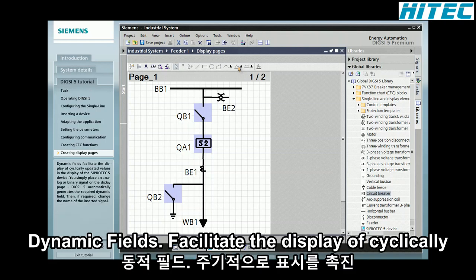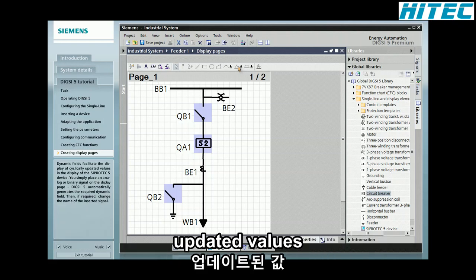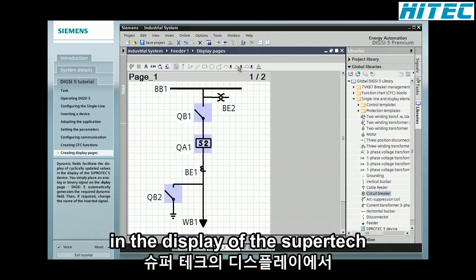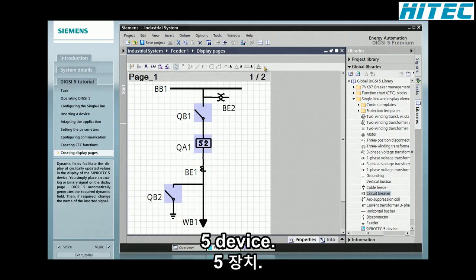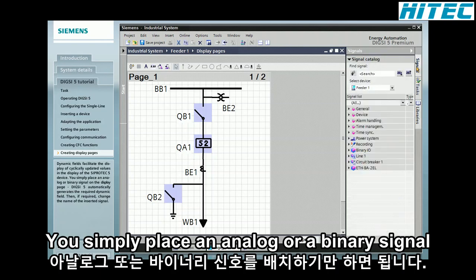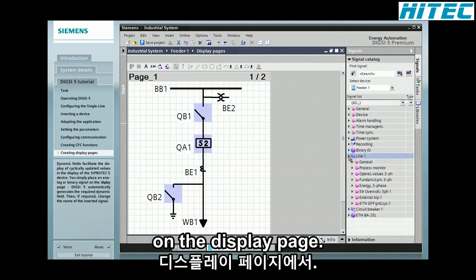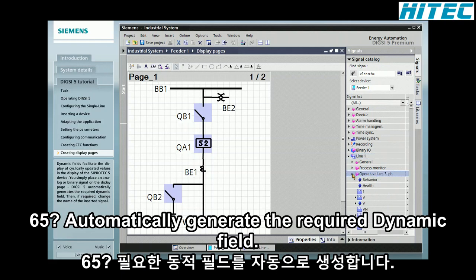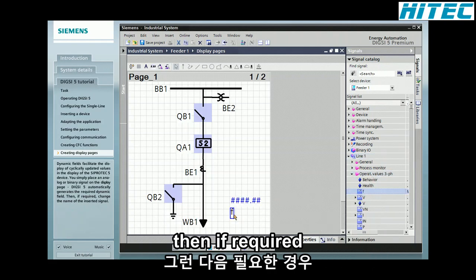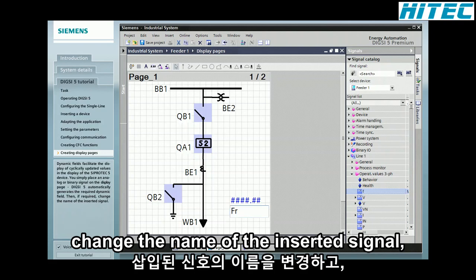Dynamic fields facilitate the display of cyclically updated values in the display of the SIPROTEC 5 device. You simply place an analog or binary signal on the display page. DIGSI 5 automatically generates the required dynamic field. Then, if required, change the name of the inserted signal.